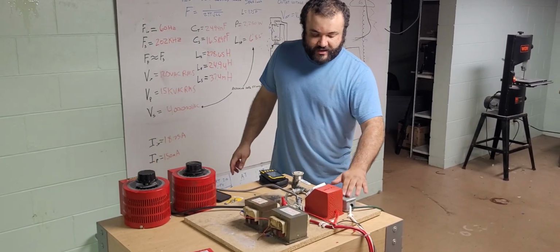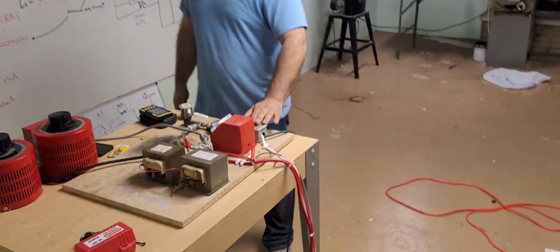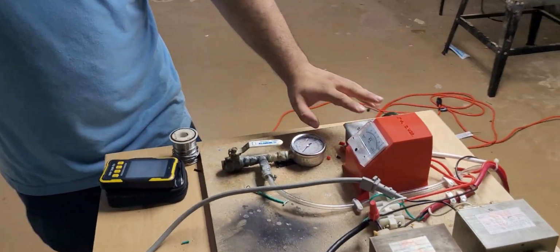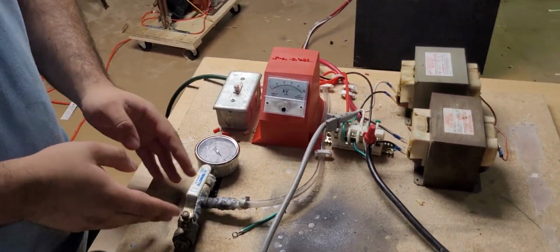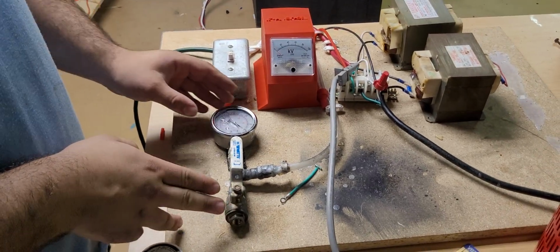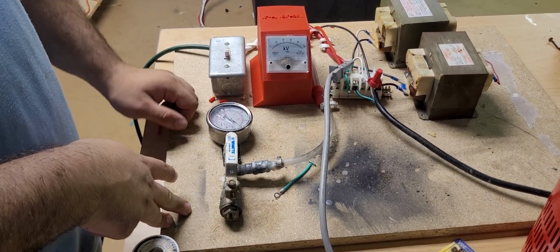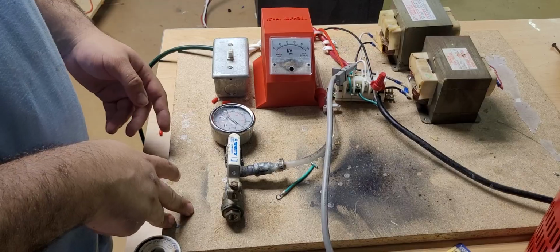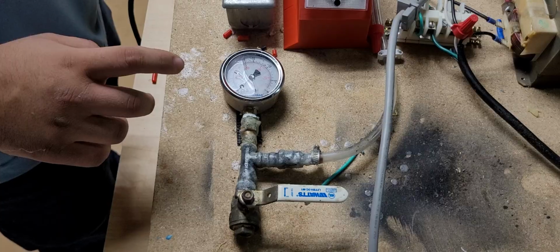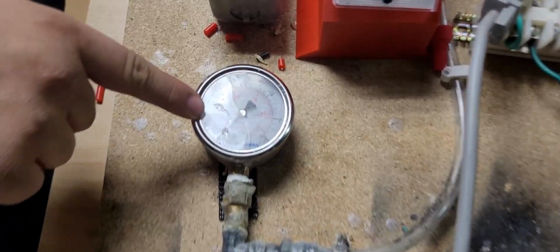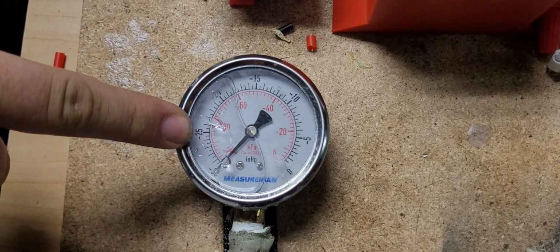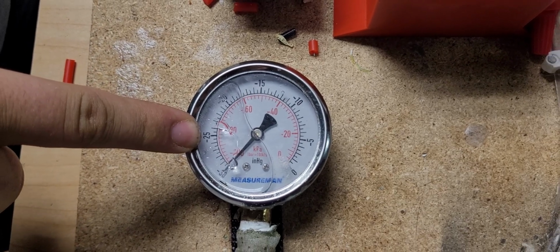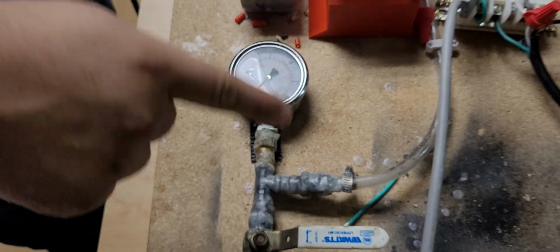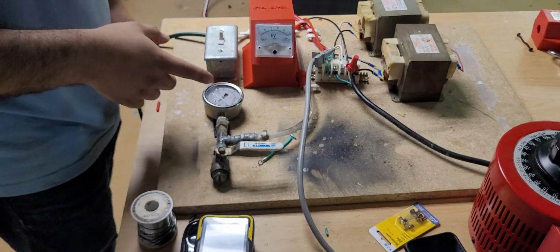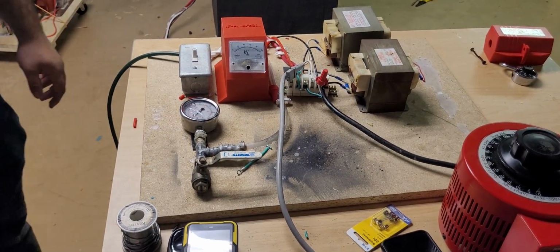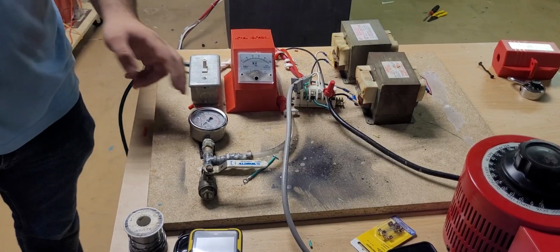And then over here we have the switch that turns power onto the pump. And here we have the gauge and the relief valve for pressure in the chamber. So we're going to go ahead and turn that on, get the pressure rolling in the chamber, and we'll be right back. Alright, see here we have our pressure gauge. Now negative 29.92 is perfect vacuum, which again is against theoretical laws of physics, Heisenberg's uncertainty principle and whatnot. However, we have it as low as we can get it for now.